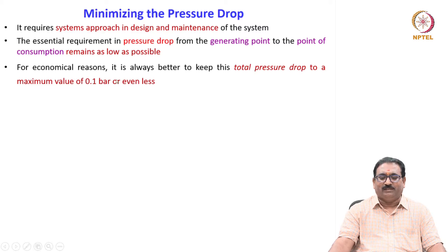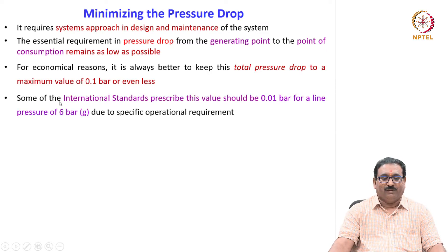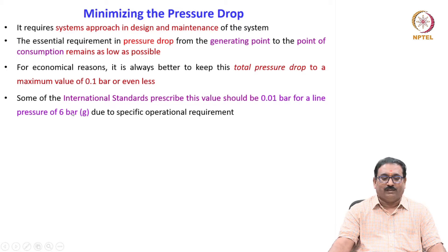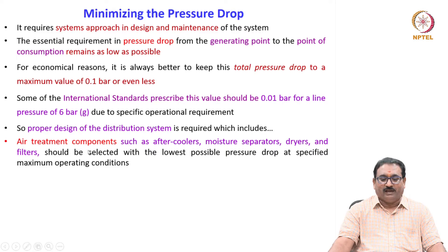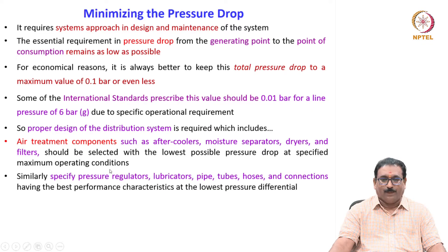For economic reasons, it is always better to keep the total pressure drop to a maximum value of 0.1 bar or even less. Some international standards prescribe this value should be 0.01 bar for a line pressure of 6 bar gauge due to specific operational requirements. Proper design of the distribution system is required, which includes air treatment components such as aftercooler, moisture separator, dryers and filters, selected with the lowest possible pressure drop at specified maximum operating conditions.